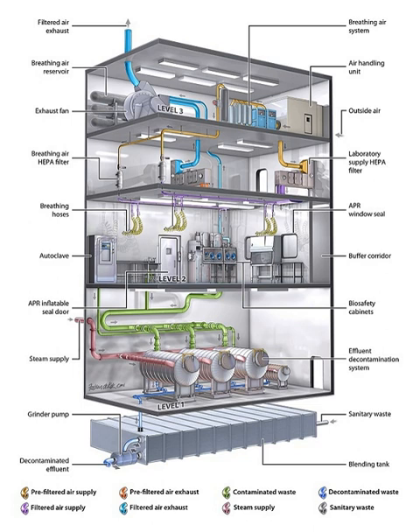In order to exit the BSL-4 laboratory, personnel must pass through a chemical shower for decontamination, then a room for removing the positive pressure suit, followed by a personal shower. Entry into the BSL-4 laboratory is restricted to trained and authorized individuals, and all persons entering and exiting the laboratory must be recorded. As with BSL-3 laboratories, BSL-4 laboratories must be separated from areas that receive unrestricted traffic. Additionally, air flow is tightly controlled to ensure that air always flows from clean areas of the lab to areas where work with infectious agents is being performed. The entrance to the BSL-4 lab must also employ airlocks to minimize the possibility that aerosols could be released from the lab. All laboratory waste, including filtered air, water, and trash must also be decontaminated before it can leave the facility. Biosafety Level 4 laboratories are used for diagnostic work and research on easily transmitted pathogens which can cause fatal disease.